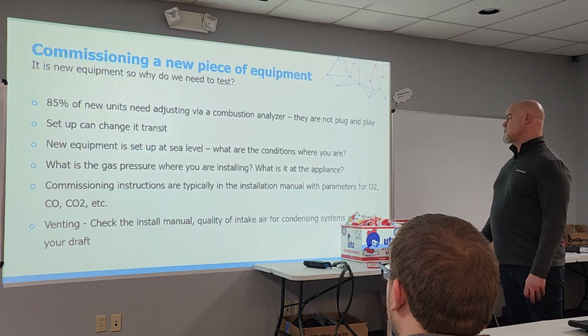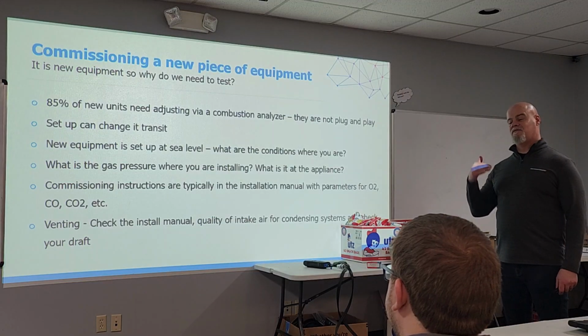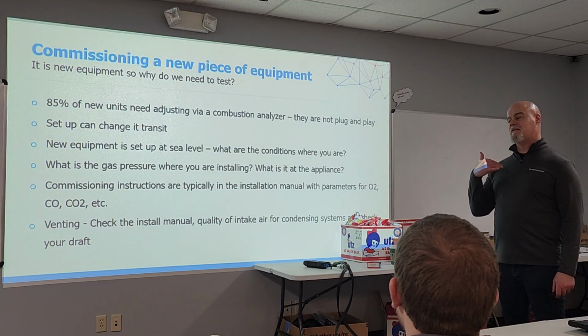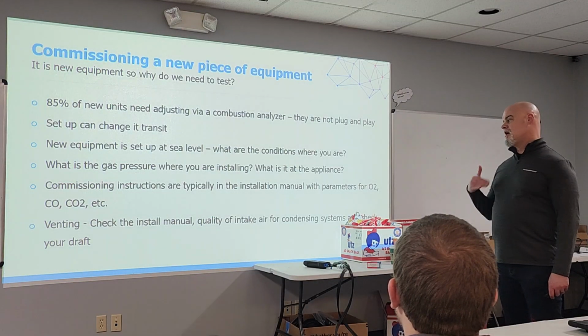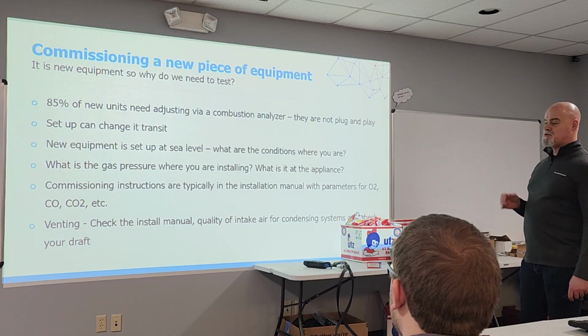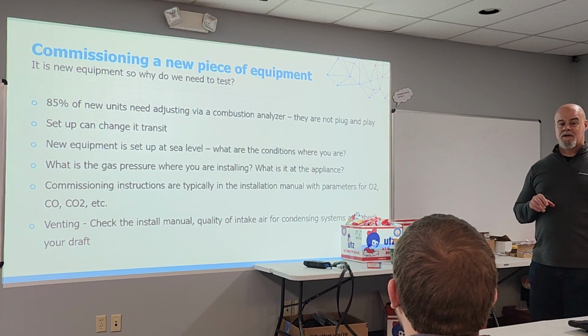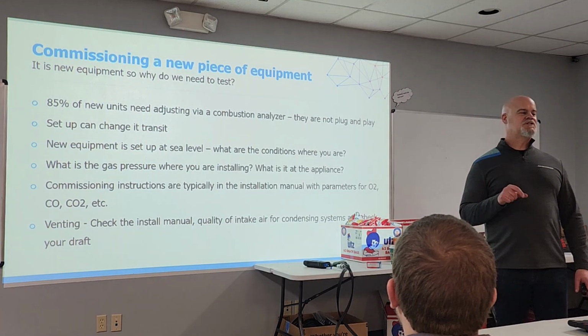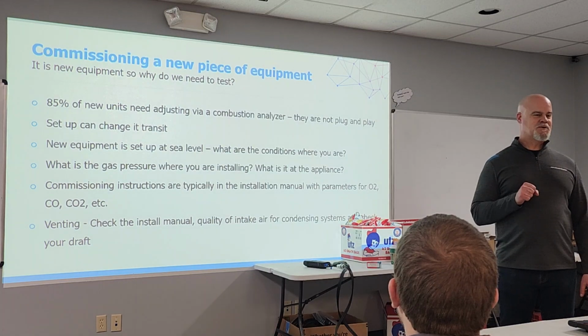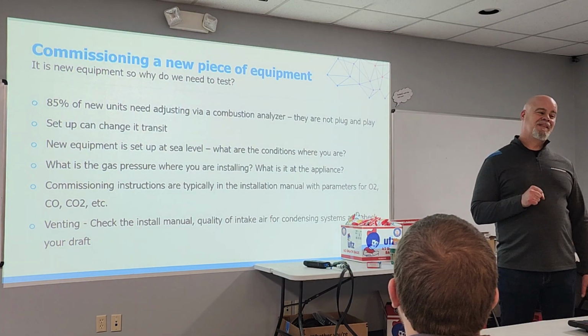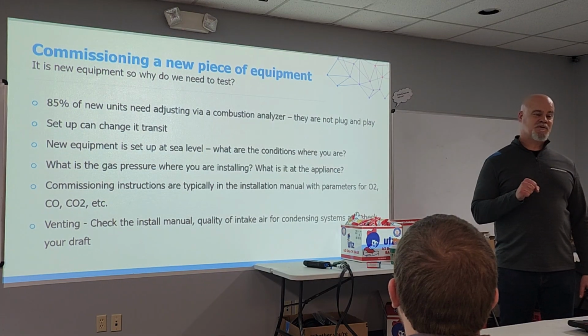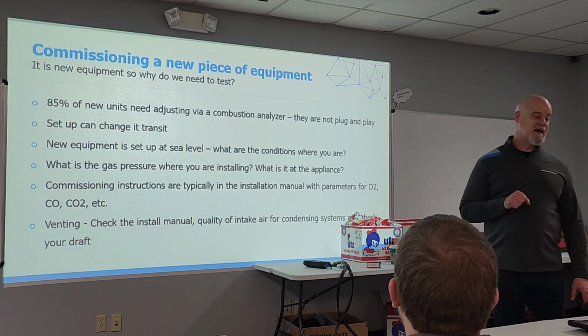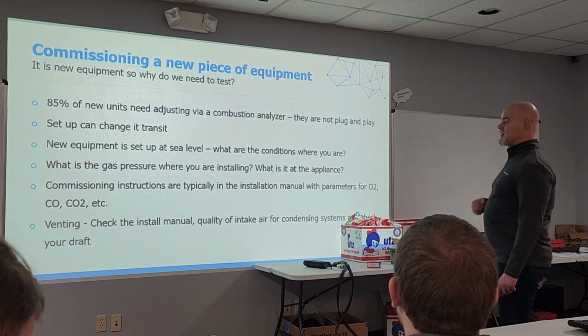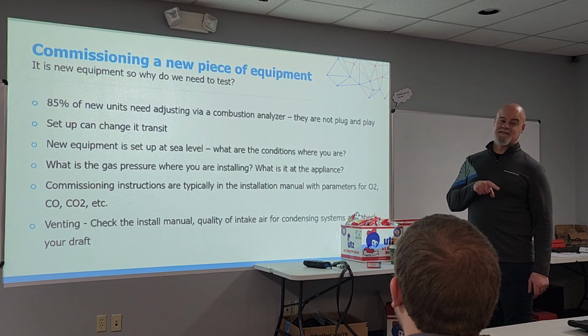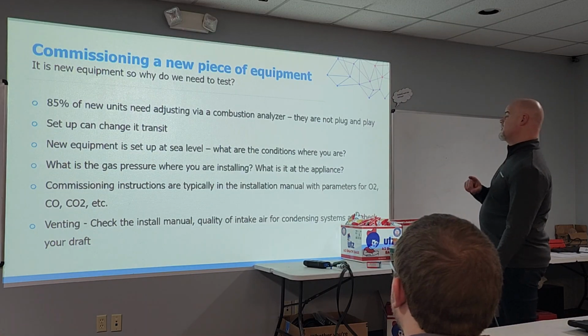What is the gas pressure where you're installing? Be very cognizant of that. Fuel flow rates can vary from place to place, day to day, so always clock that meter. Also be careful, in certain parts of the country this has happened to me, they change the BTU content of your fuel in extremely cold weather. They pump it up with a bit of nitrogen, which makes your pressures and everything else a little wacky. The gas company won't tell you that, but that's what they do. So be cognizant of that. It helps to have friends who work for the gas company, they give you the inside track on this stuff.